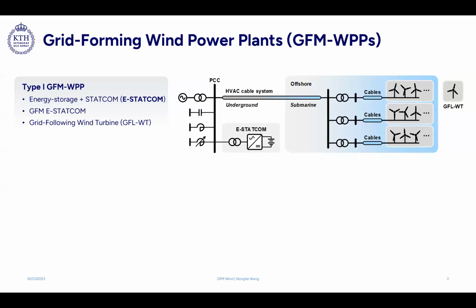So today I will talk about 2 types of grid forming wind power plant. The type 1 is based on grid following wind turbines with the standard design. And then we put the STATCOM with energy storage. That is what we call the enhanced STATCOM, eSTATCOM. This eSTATCOM is configured with grid forming control. In this way, we try to provide grid forming capability at the point of common coupling.